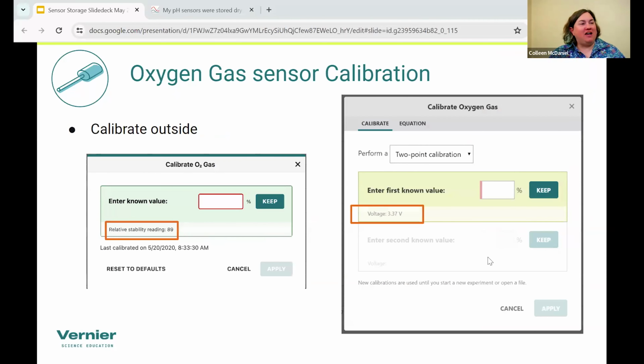This just gives you a view of what the calibration is going to look like, depending on whether it's a LabQuest sensor or a Go Direct sensor. I always recommend going outside to calibrate your oxygen gas sensor, same thing with the CO2. It's best to be in atmospheric conditions, because when you're inside, there's a lot less air movement and more CO2 buildup, so you won't get as good of an oxygen reading.